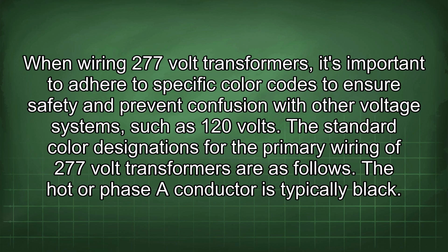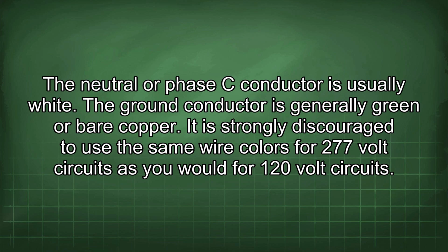The standard color designations for the primary wiring of 277-volt transformers are as follows: the hot or phase A conductor is typically black, the neutral or phase C conductor is usually white, and the ground conductor is generally green or bare copper.